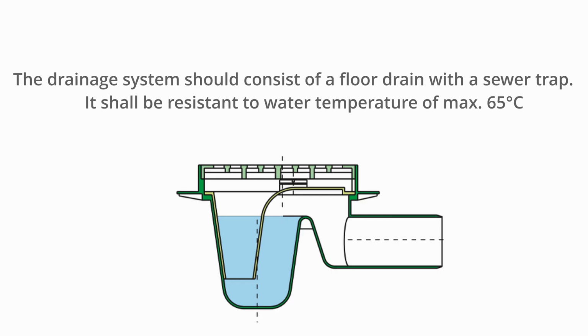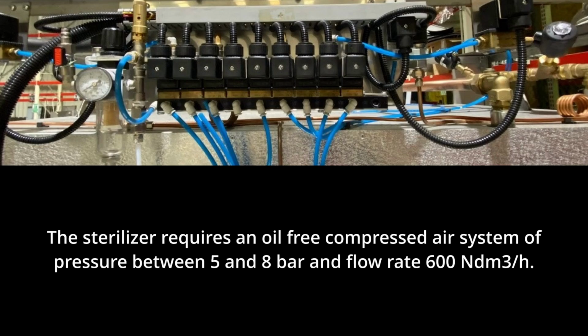The drainage system should consist of a floor drain with a sewer trap. It shall be resistant to water temperature of maximum 65 degrees. The sterilizer requires an oil-free compressed air system of pressure between 5 and 8 bars and flow rate of 600 normal cubic decimeters per hour.